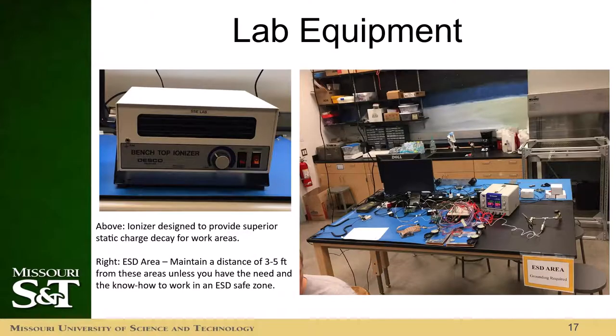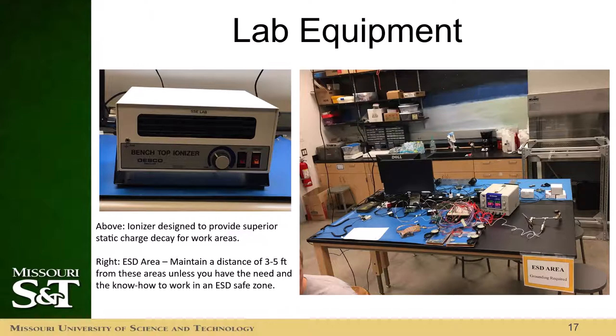We provide lab equipment to make ESD mitigation easier. On the left is an air ionizer, which is designed to ionize the air and allow charges to dissipate more easily. On the right are ESD areas, which can generally be identified by the blue mats — you might even see the ionizer on the table. If you don't need to be in a certain area, staying away from it is the best way to avoid an accidental ESD event.